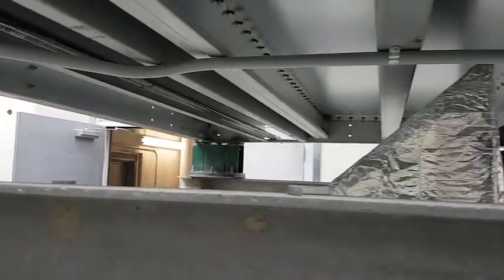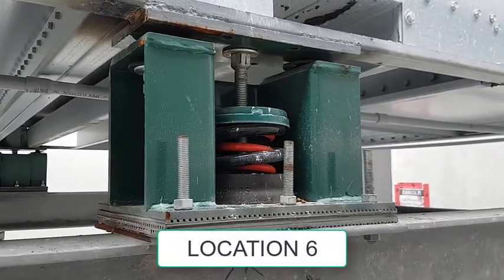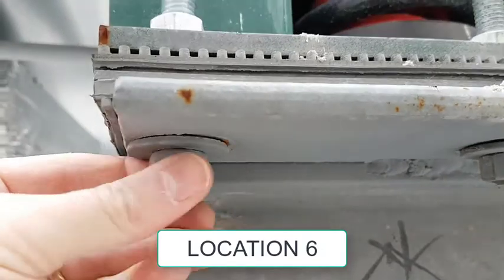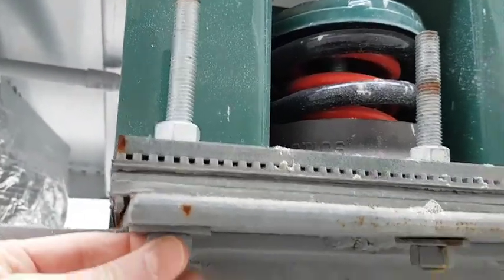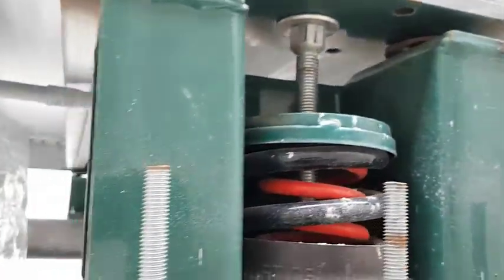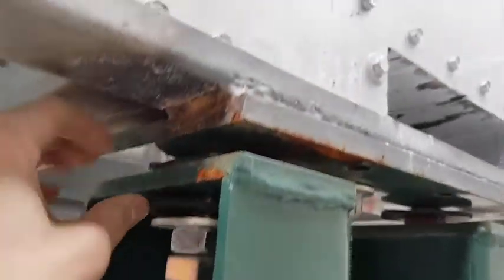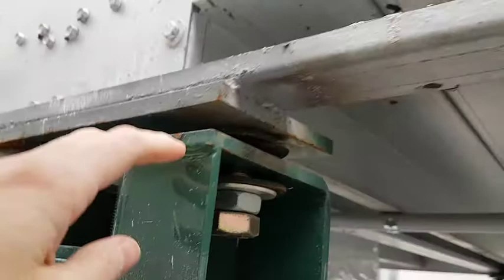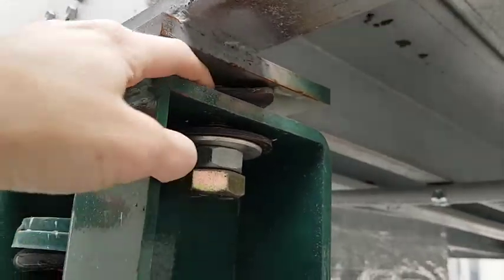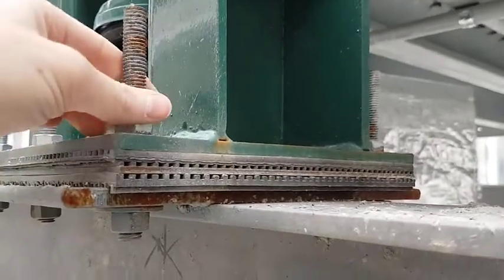Next is location 6, and as expected, the outer spring is black and the inner spring is red. Checking the bolts, I find that one of them is loose. It appears the contractor chose to cut costs and used cut pieces of threaded rod with nuts instead of proper bolts, washers, and nuts. The hold-down bolts appear okay, and there's plenty of gap between the top plate and hold-down plate on both sides, though perhaps just slightly more than necessary. The neoprene pad appears okay here too.